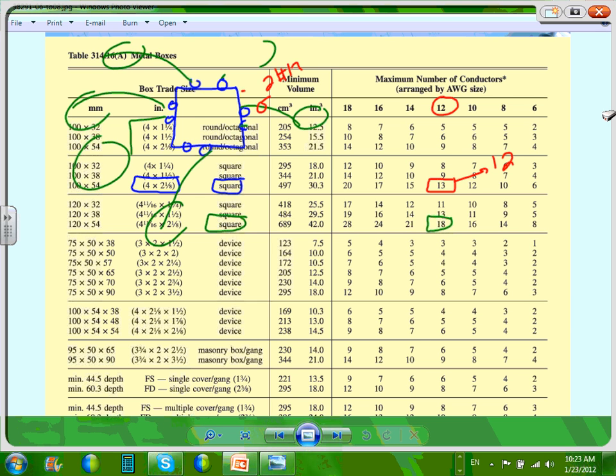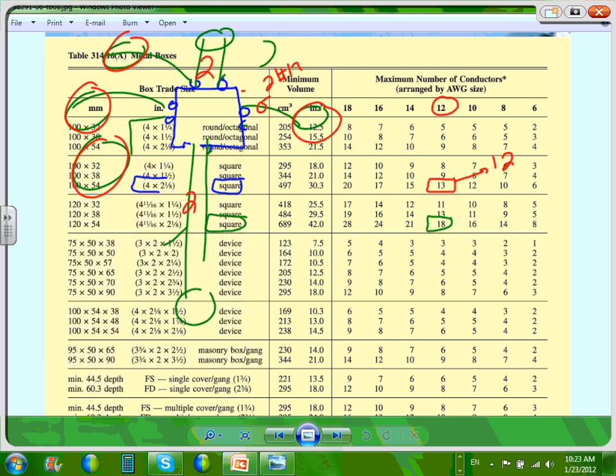you might have to be very careful, like you said, because you have a conduit coming in and a conduit coming out, and you have 2 conductors in this conduit and 2 conductors in this conduit. That's why you are limited to a 4. 1, 2, 3, 4. 4 lights, because you have 2 conductors in and 2 conductors out to go to a different location. 4 fixture wires in a J box is a good limit to use as a design. Does that make sense?